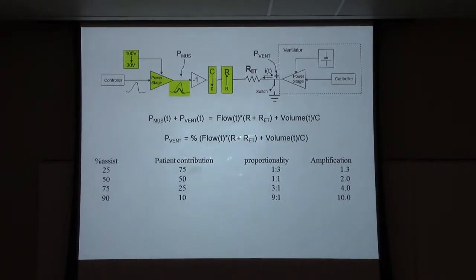So if one goes up, the other one goes up, right? If the patient pulls harder and increases flow and volume, then this term increases and P-vent will increase, right? But they have to go in the same proportion. So now if you set it to 25%, the patient is contributing 3/4 of all the voltage. The proportionality is 1:3. And amplification, in other words, it's as if you've increased this by 30%.